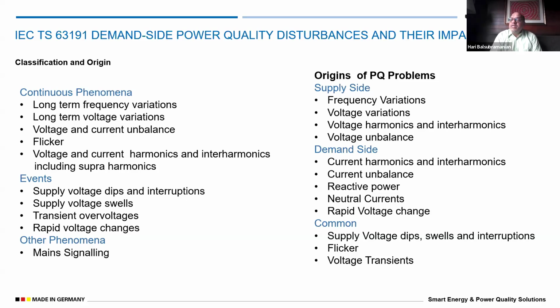Where are the origins of these power problems? On one side I have said short-term events, long-term events, but where are their origins? They can be from the supply side or also from the demand side. Supply side can be frequency variations, voltage variations, voltage harmonics and interharmonics, voltage unbalance. Demand side can be current harmonics, current unbalance, reactive power, neutral current, rapid voltage change. Some of these can be common to either the supply side or demand side, such as voltage sags, swells and interruptions, voltage transients, and flicker.